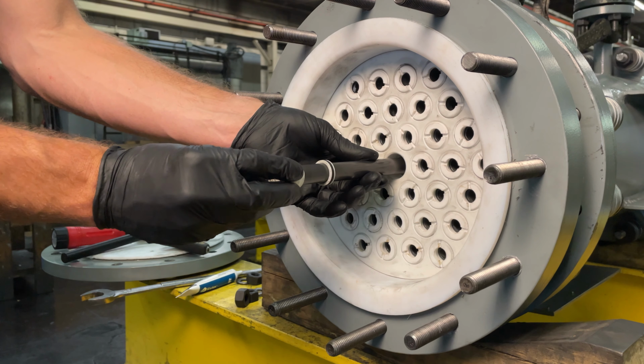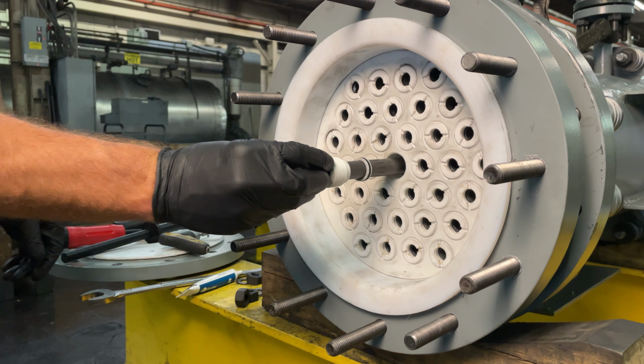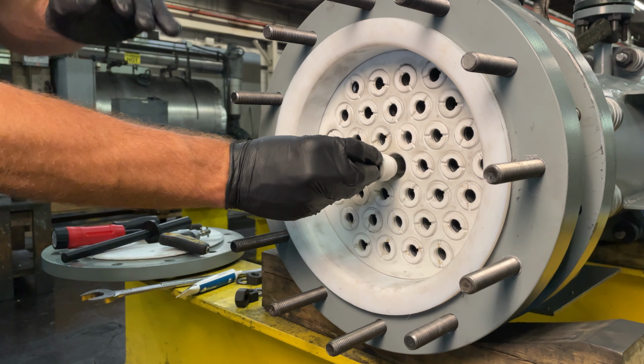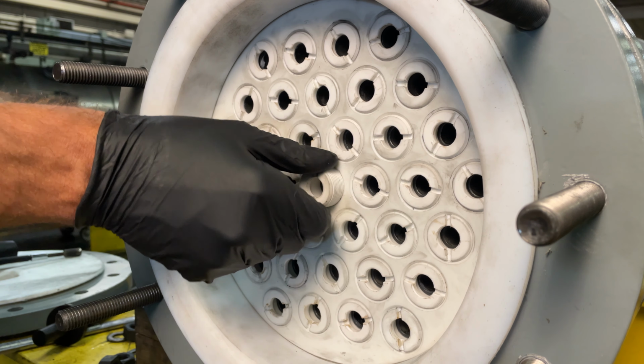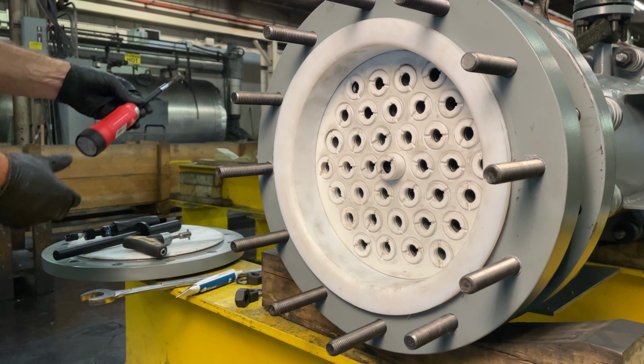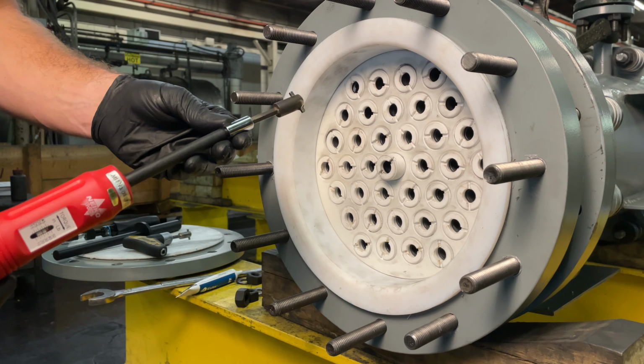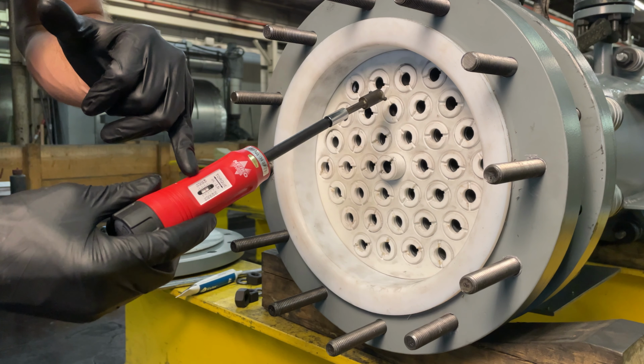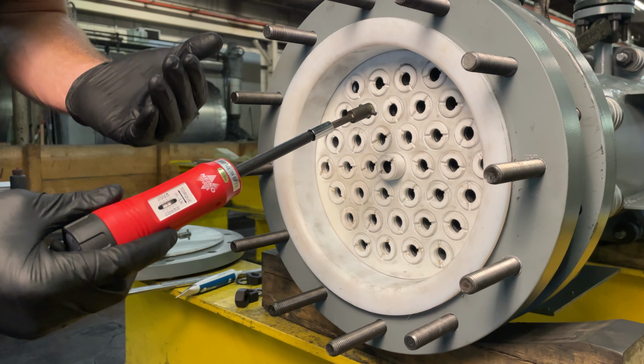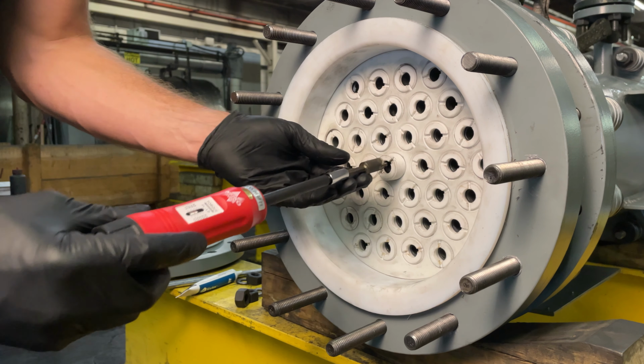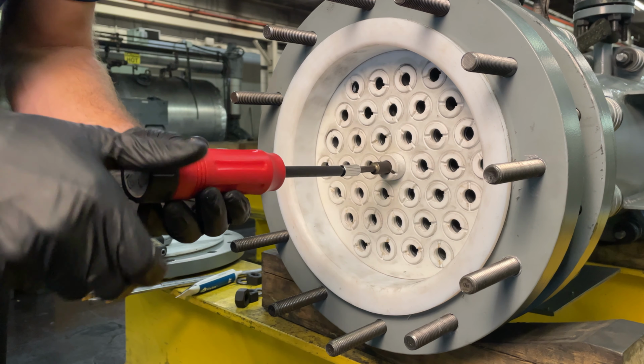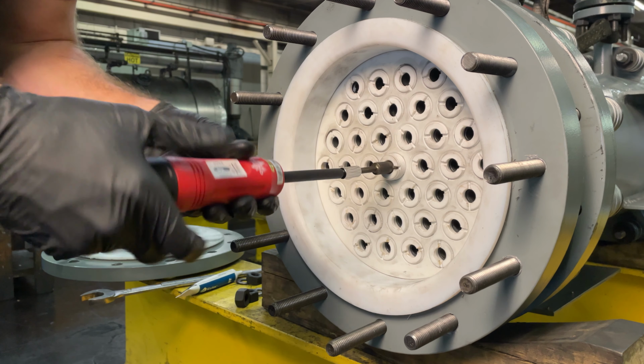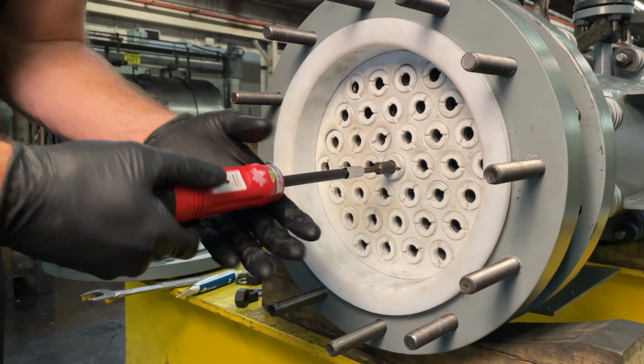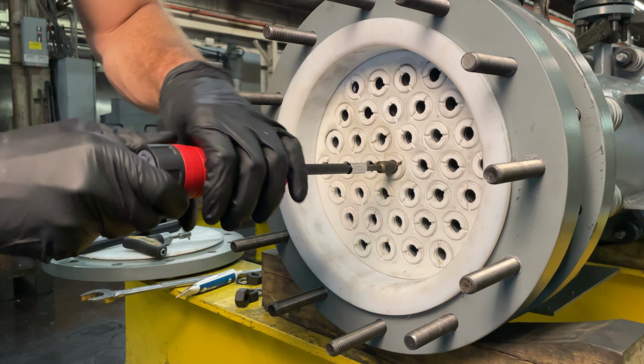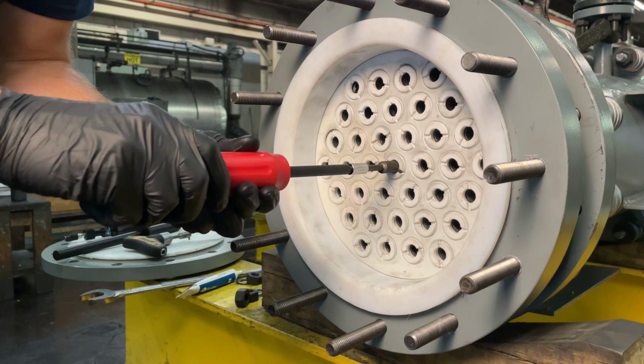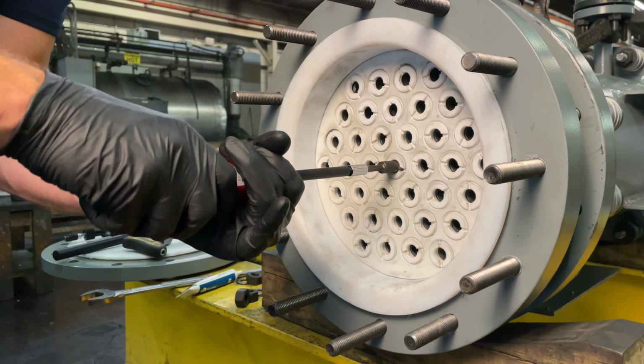Insert the tube nut by hand initially to avoid cross-threading and damage to the threads on the tube sheet. You'll then take your torque screwdriver. In this case, 30 inch-pounds is the appropriate setting from the assembly drawing. Begin to tighten the tube nut. The screwdriver will click to let you know when you've reached the nominal torque.